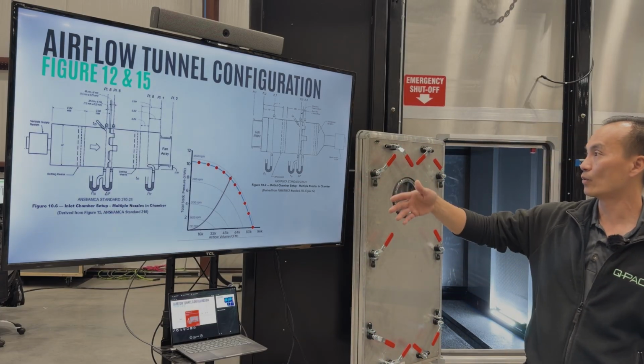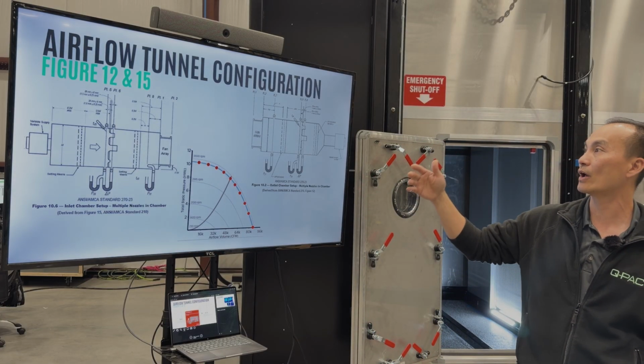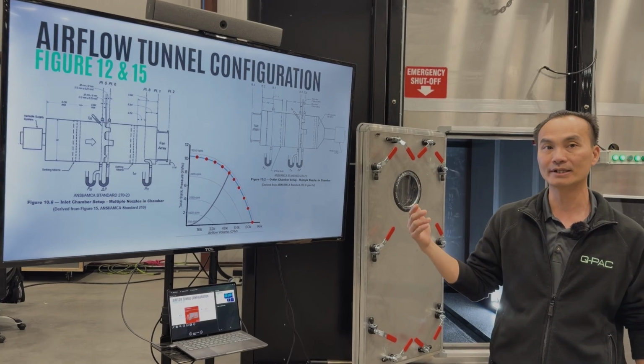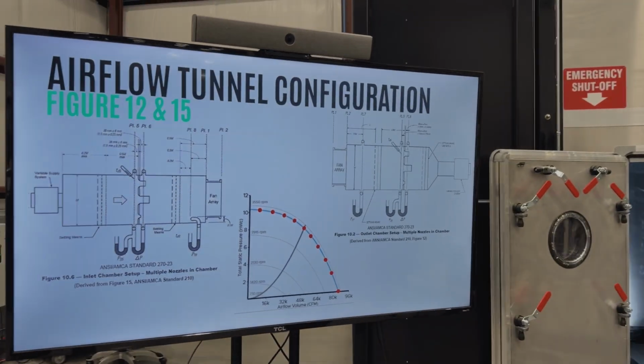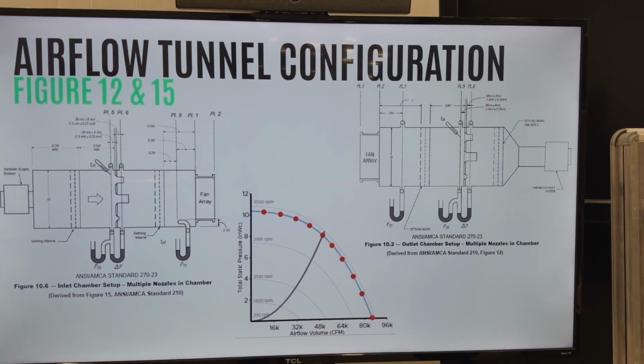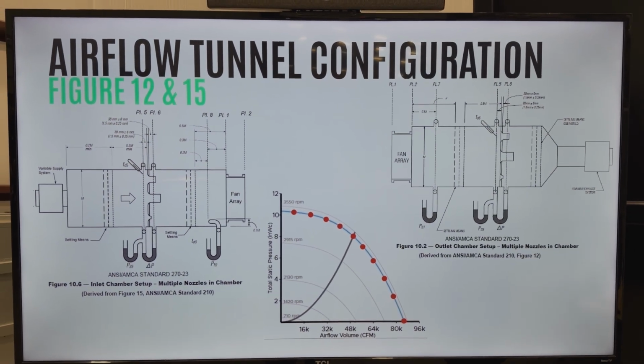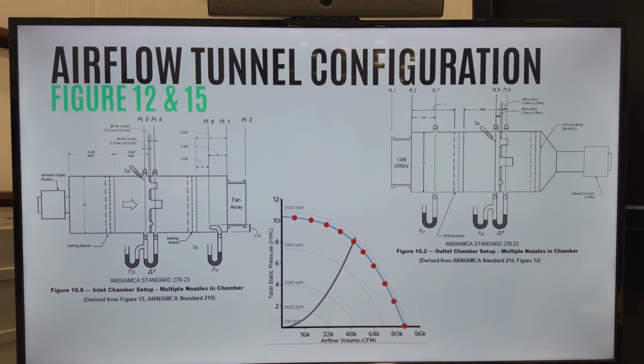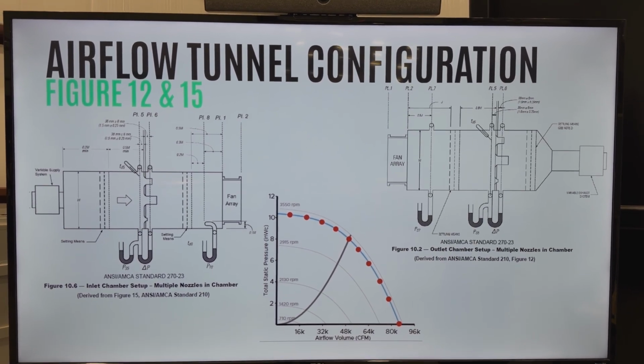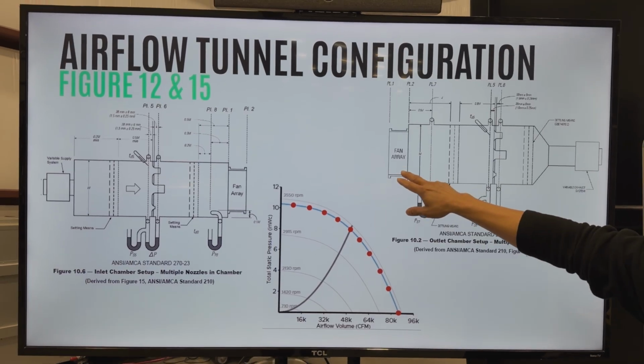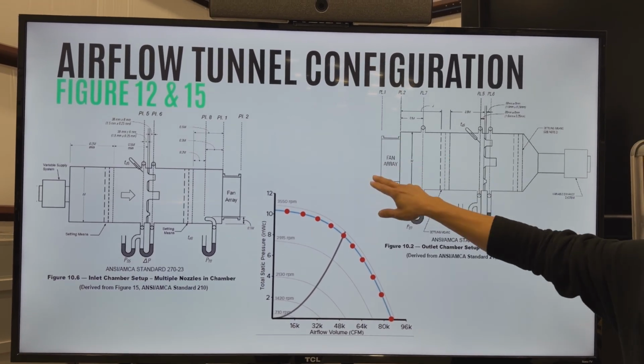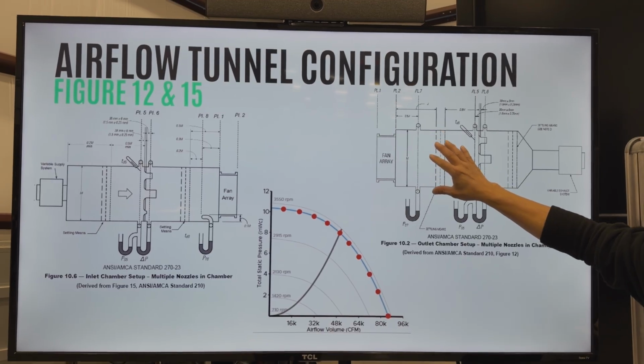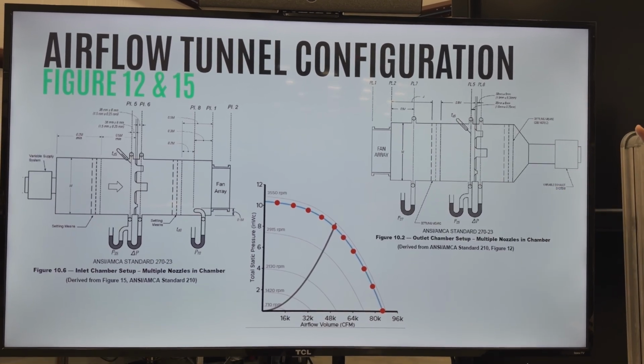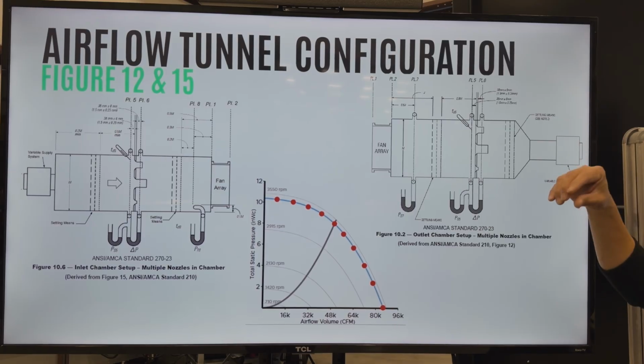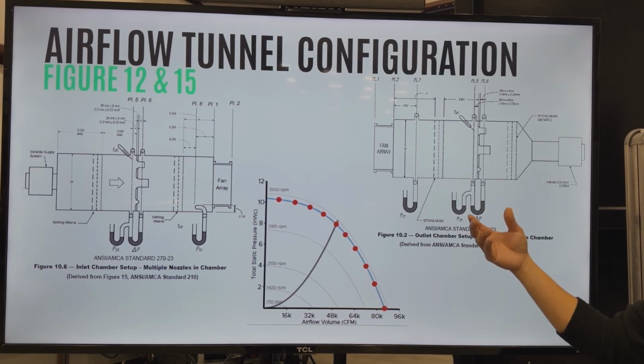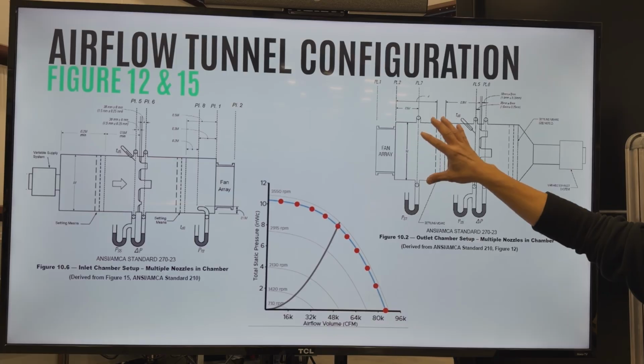Here we want to show a diagram of the airflow tunnel. Again, the airflow tunnel is designed from Figure 12 and Figure 15. What is the difference? It means our test fan is exhaust, or our test fan could provide the air into the airflow tunnel. If you look at this configuration, if this is the air handling unit providing the air into the airflow tunnel, we can use the tunnel to simulate every single thing, like the ductwork and the effect of the coil, and how the fan would behave with it. So this is how we test at the system level.